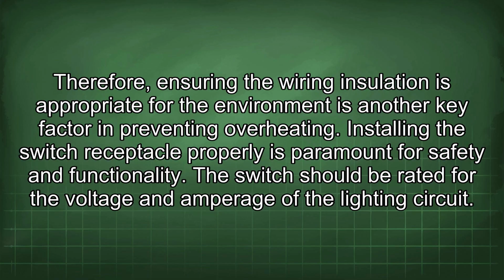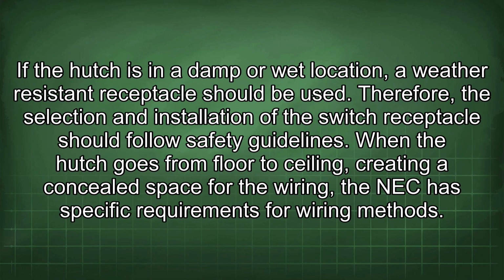Installing the switch receptacle properly is paramount for safety and functionality. The switch should be rated for the voltage and amperage of the lighting circuit. If the hutch is in a damp or wet location, a weather-resistant receptacle should be used. Therefore, the selection and installation of the switch receptacle should follow safety guidelines.